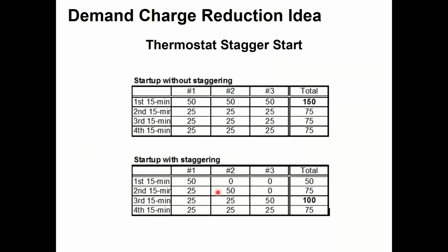You can do this manually with your thermostats as well. In this case, I have 3 thermostats, and we're starting them all at different times. In this example, they have a 50 kW demand and a 25 kW runtime. So if I started them all at the same time, I would get an inrush of 150. Right? If I happen to start them all at the exact same time.